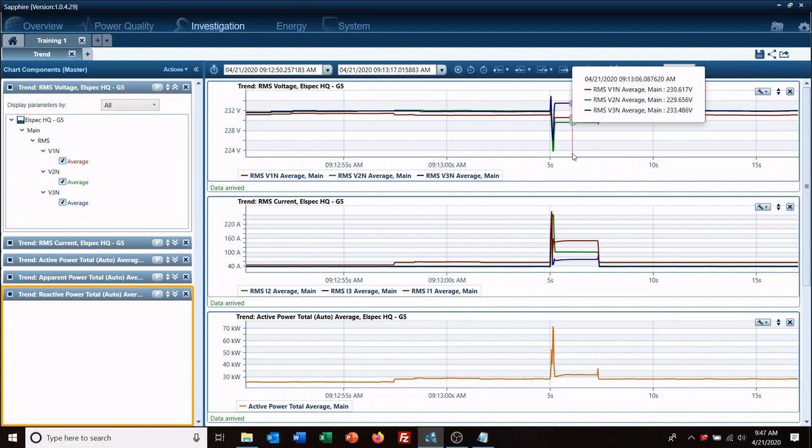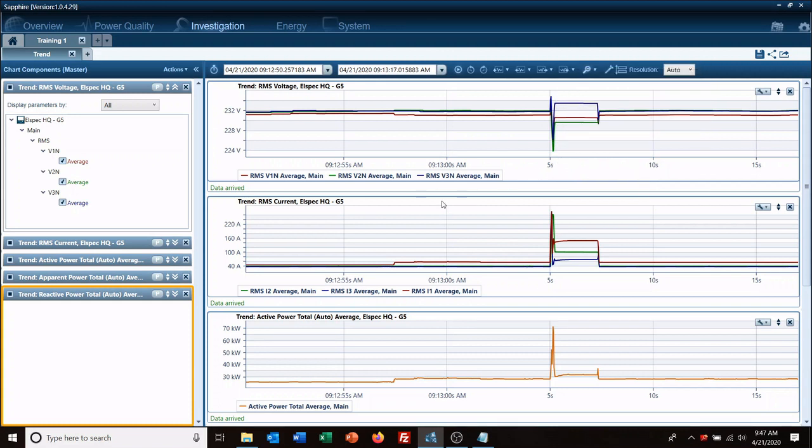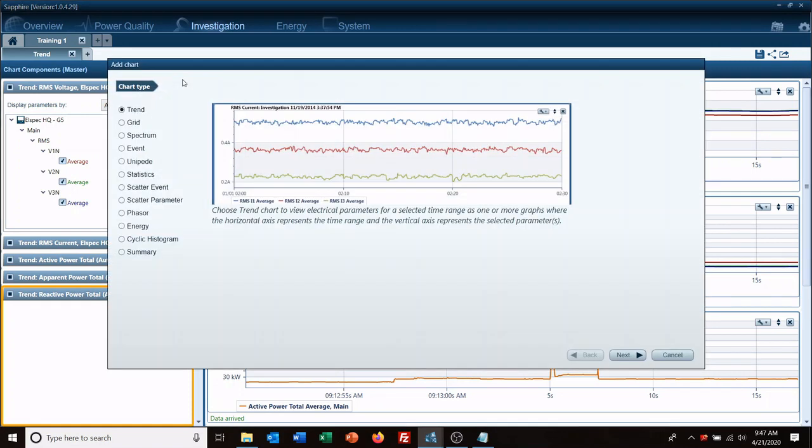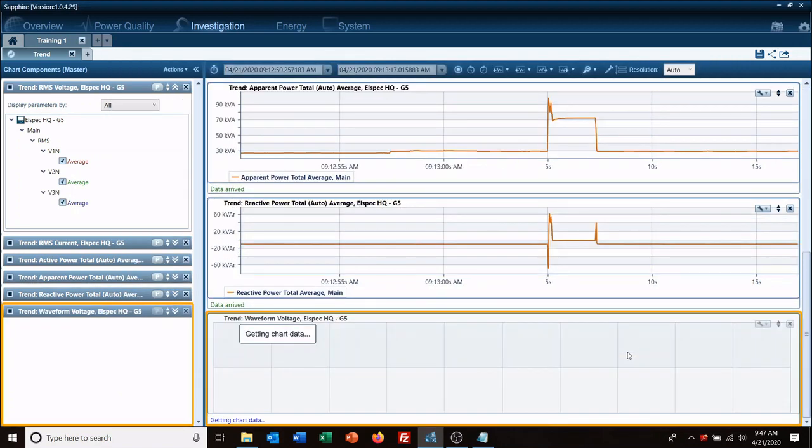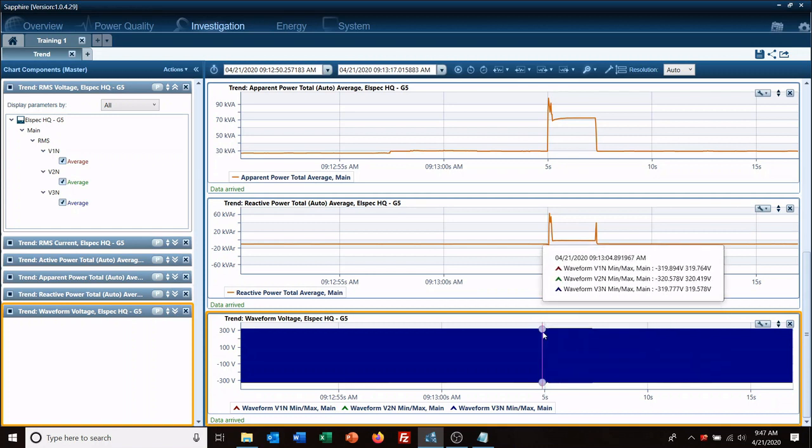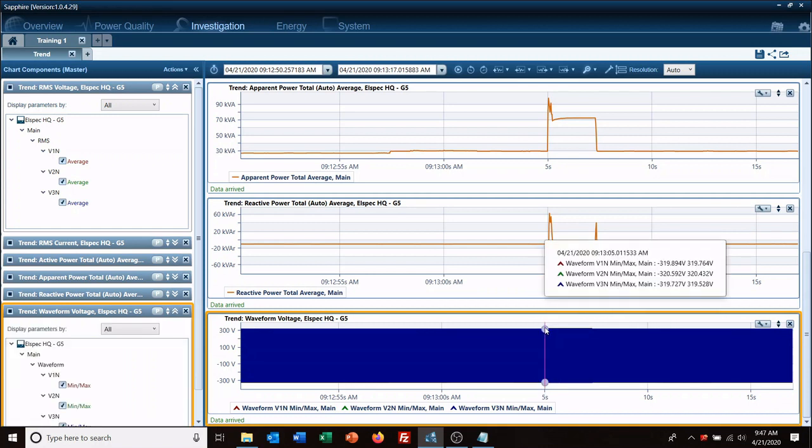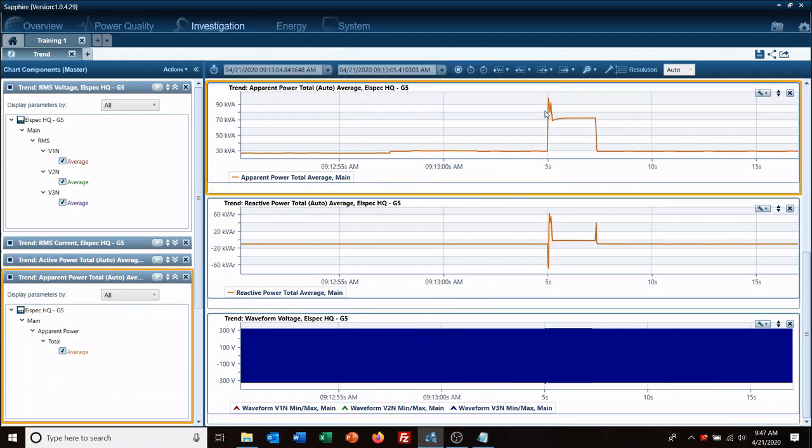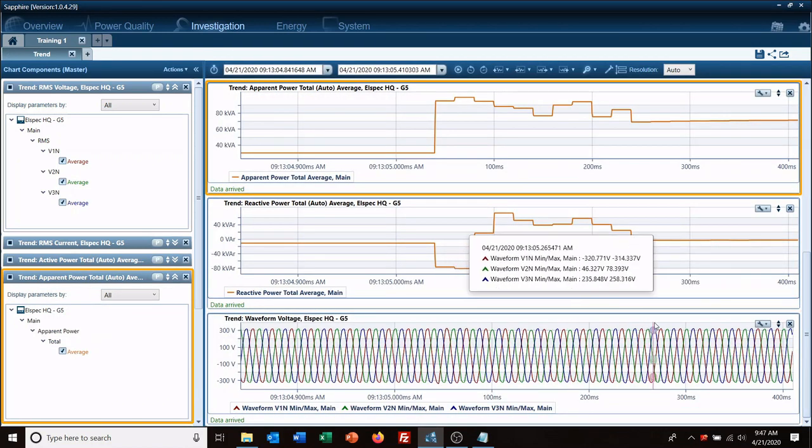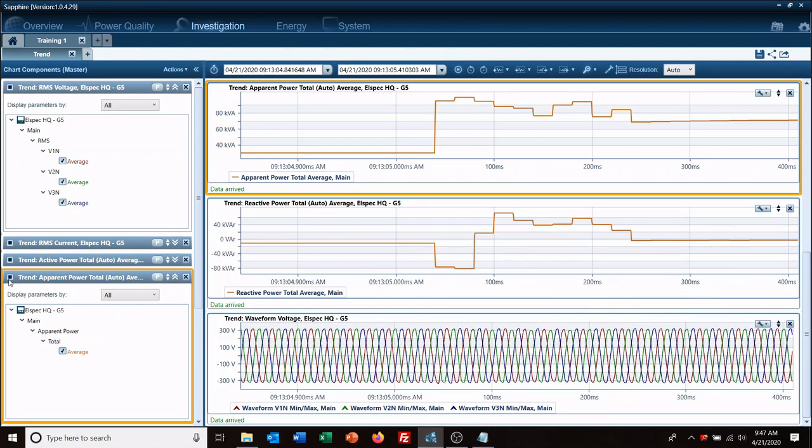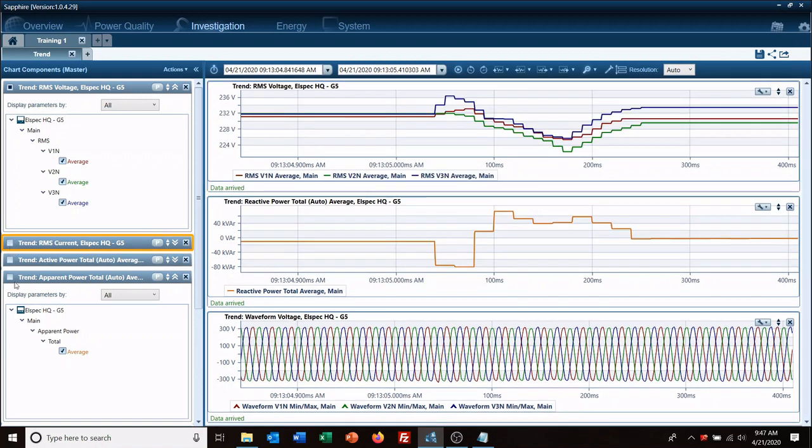And say I'm looking at this again, I'd really like to see what the waveform's doing at this point. So I can go actions, add new chart, trend, and then waveform. We'll look at our voltage waveform and now we can see there is the same little corresponding bump right here.